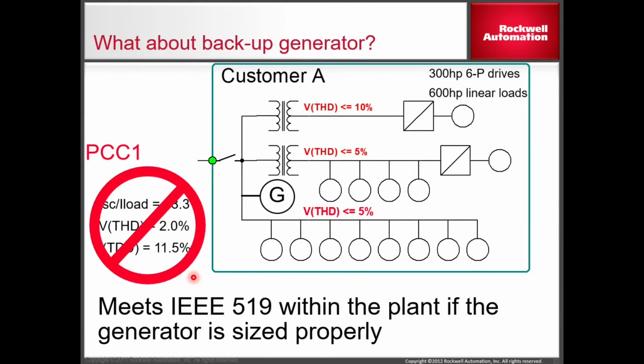Now, if you have a generator in your plant, there's a rule of thumb when you have 6-pulse drives that you need to take the load of those 6-pulse drives and multiply it by 3.